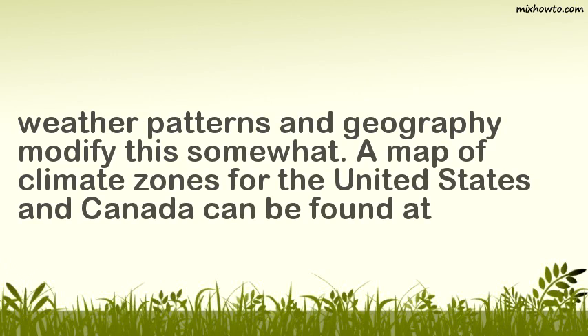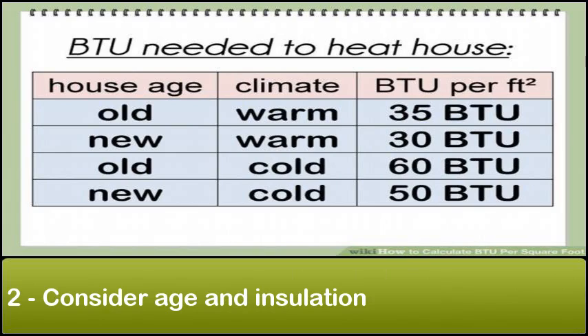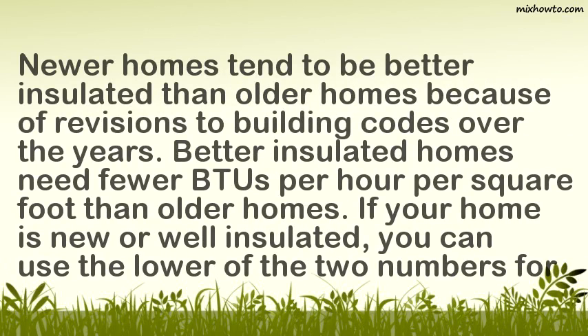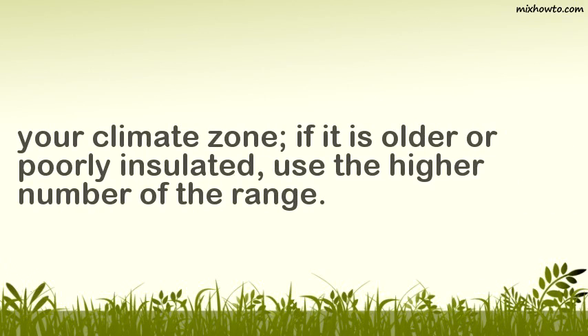Consider age and insulation. Newer homes tend to be better insulated than older homes because of revisions to building codes over the years. Better insulated homes need fewer BTUs per hour per square foot than older homes. If your home is new or well insulated, you can use the lower of the two numbers for your climate zone; if it is older or poorly insulated, use the higher number of the range.